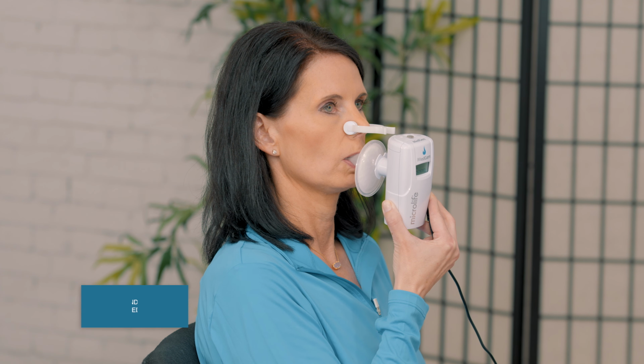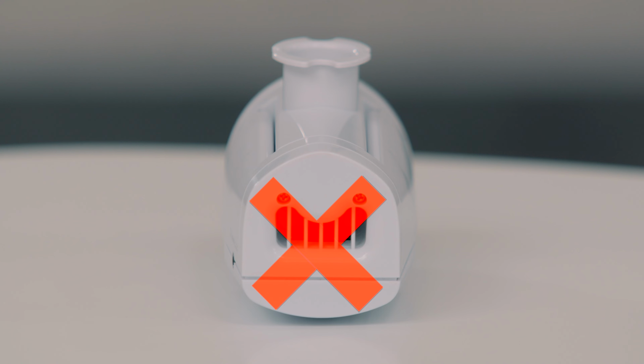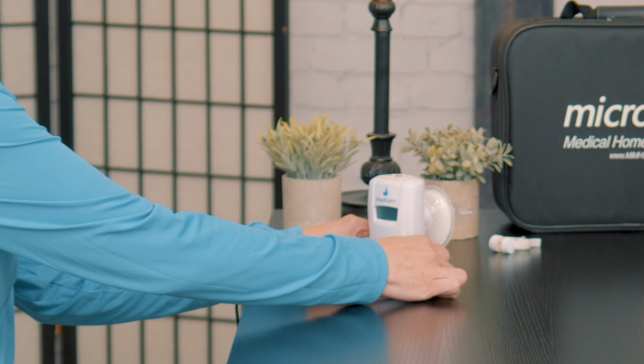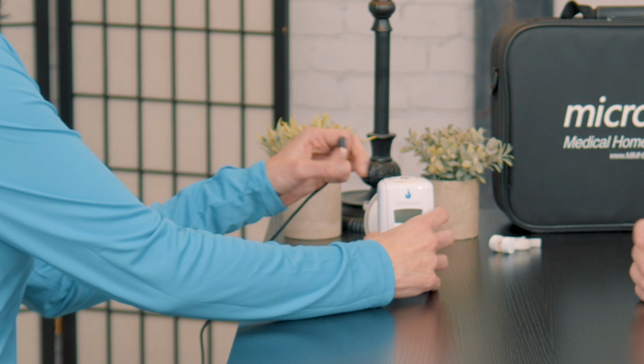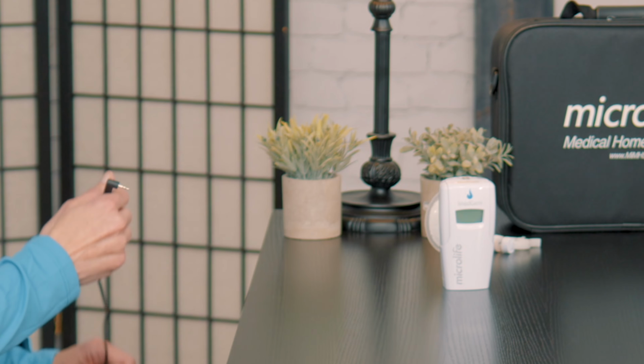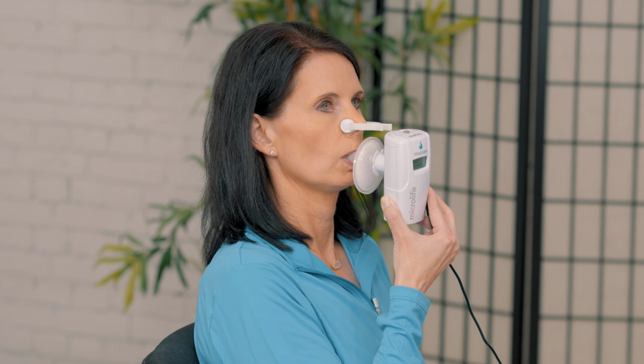Ensure that your patient has been instructed not to move during the measurement, as they will need to hold the MedGem device during the measurement. To hold the MedGem device, place your hand on the front of the unit, not on the base where gas flow will be interrupted and the measurement will be interrupted. Be careful not to dislodge the power cord during measurement, as this will discontinue the process. Make sure the patient is comfortable and the device remains stationary to avoid any measurement errors.